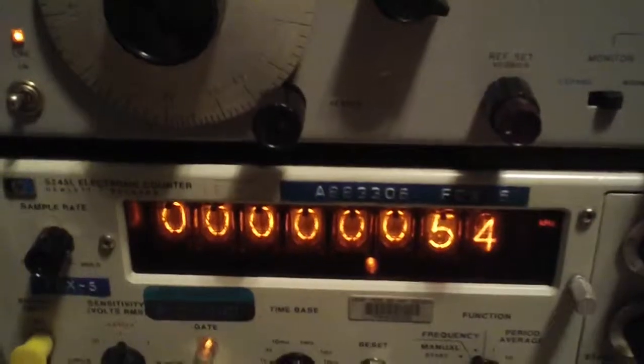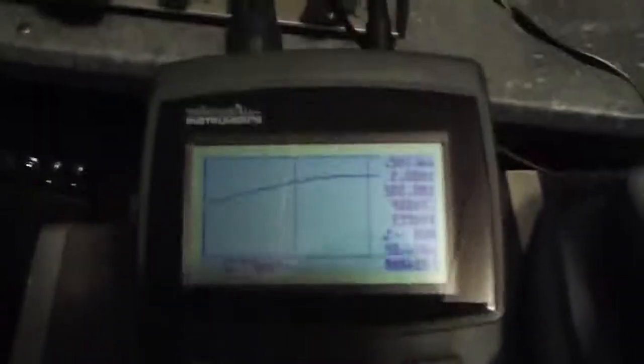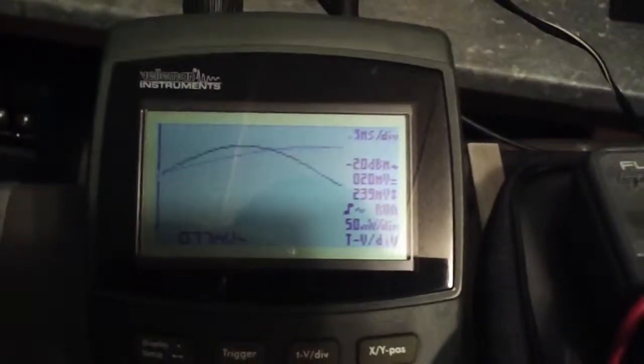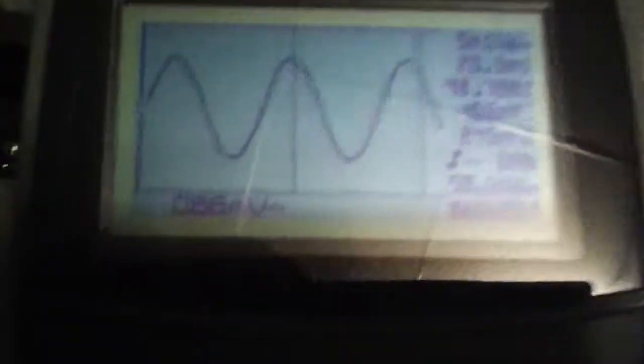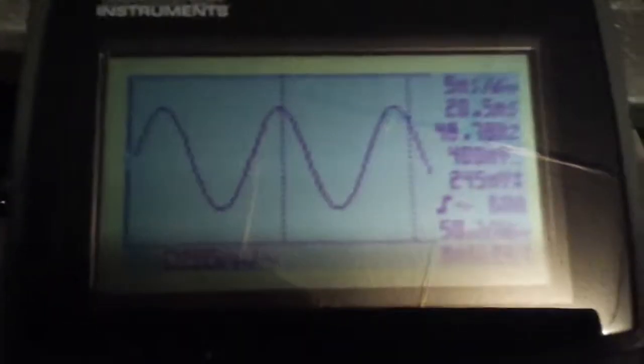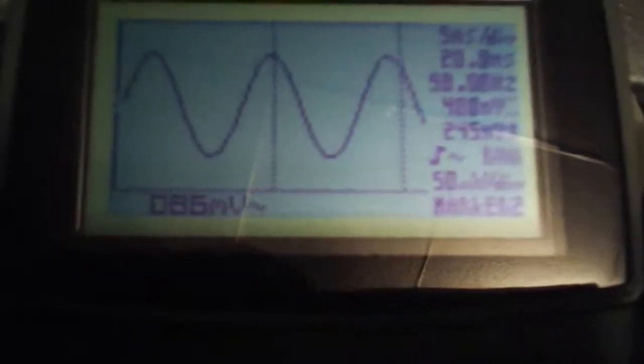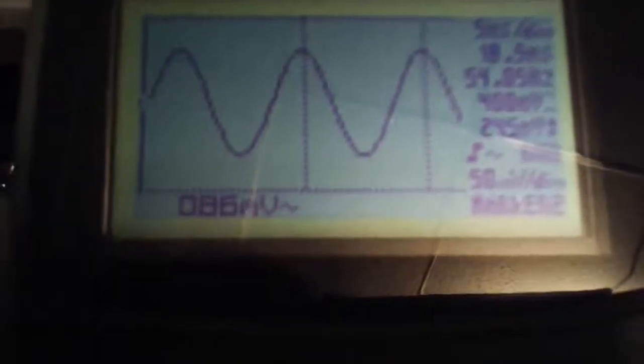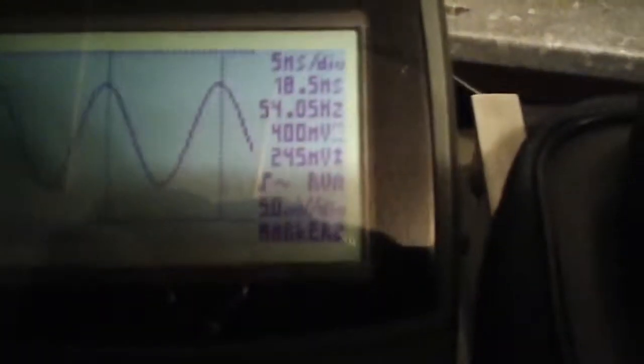So let's cut it back down to the sub-line frequencies. We're on 53, 54 hertz. Go back up to the scope — cut this down, change the time, get rid of the markers. We're seeing approximately 54 hertz.